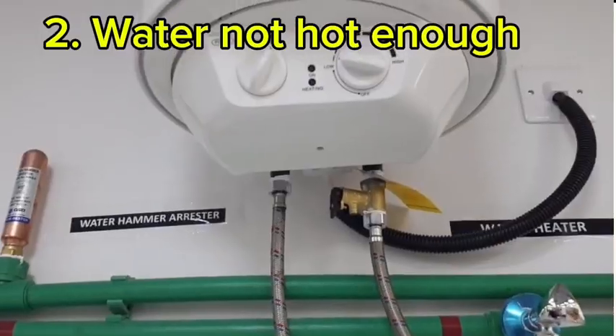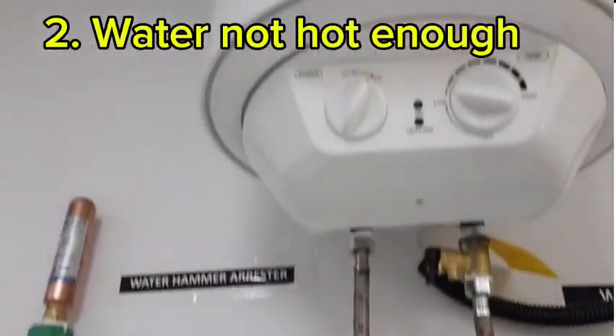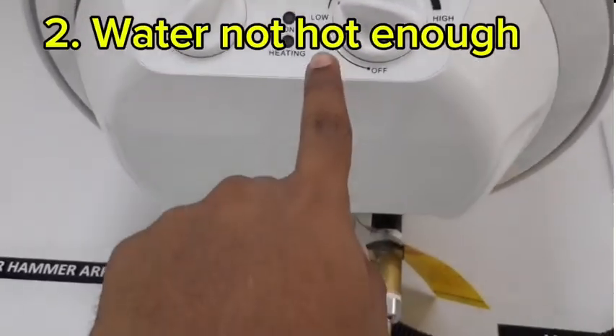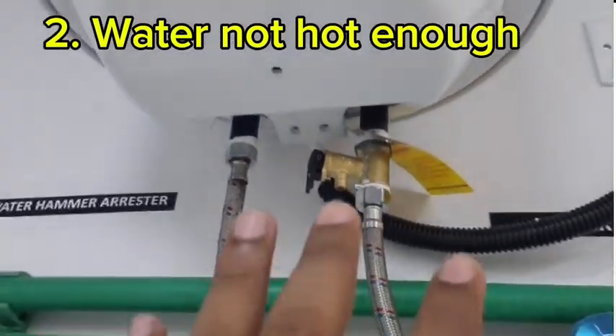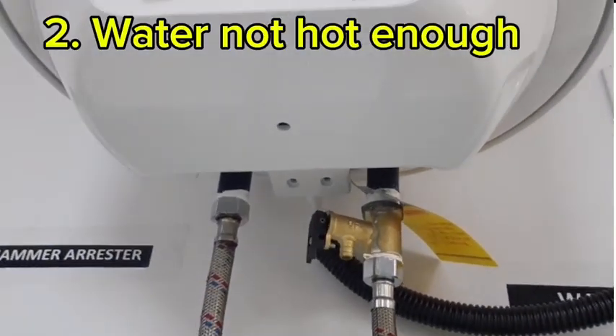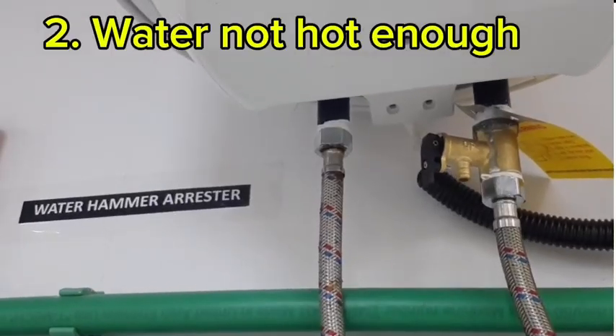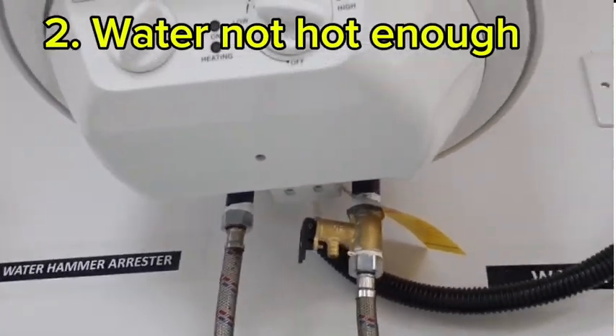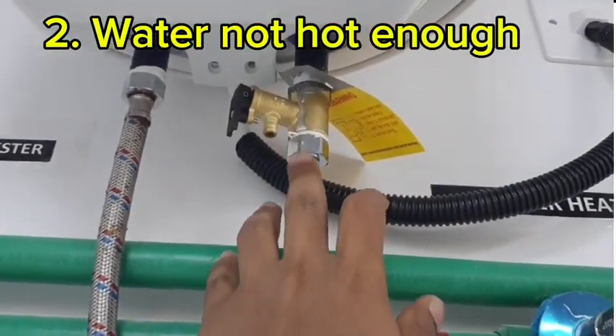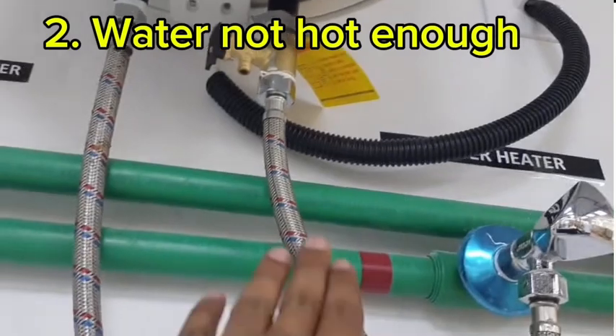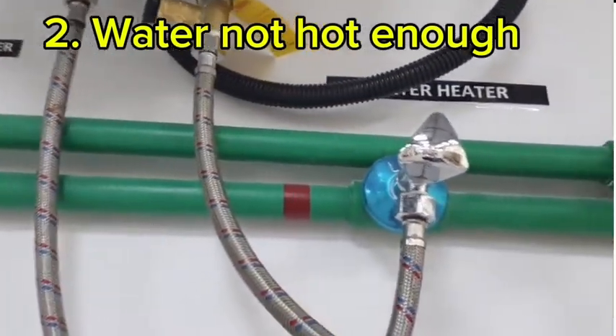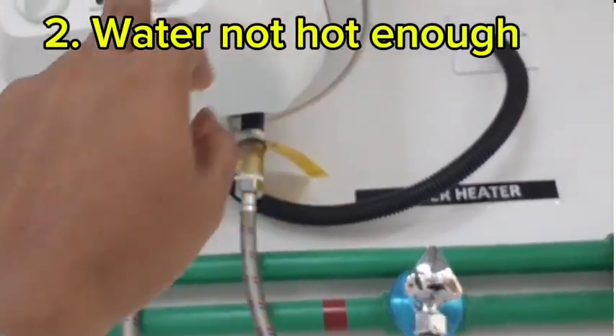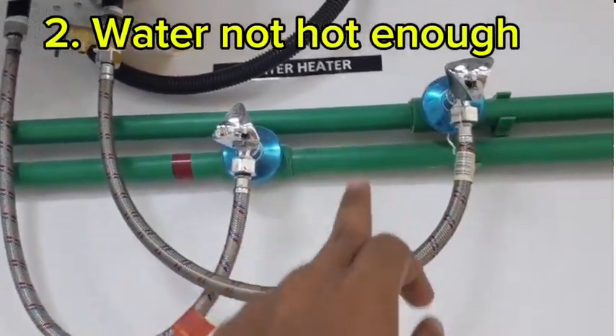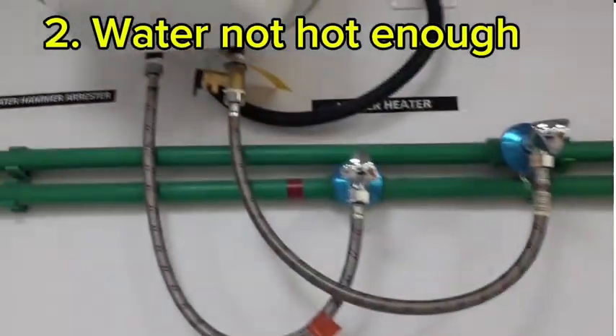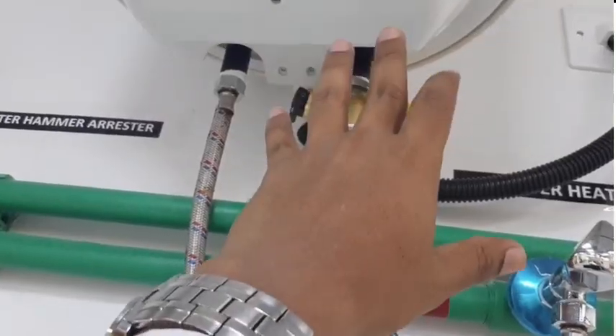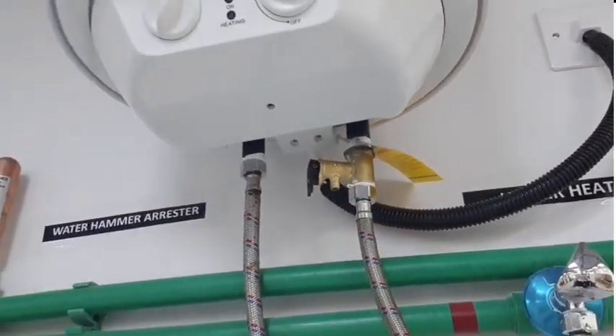So the second complaint we will discuss: water not hot enough. If the water is not hot enough, then you have to check the thermostat setting. Then scale build-up. Sometimes if you do not do preventive maintenance at regular intervals, there will be scale build-up. Third is heating element failure and excessive water demand. Sometimes you can see there is an NRV, non-return valve, installed in the inlet line. This is the inlet line, this is the outlet line. Here water comes to the water heater tank, then it is connected to the outlet line where our wash basin is connected. What will happen if this NRV fails? Then the water will not be stored inside the tank, and you will not get proper heating in the water.